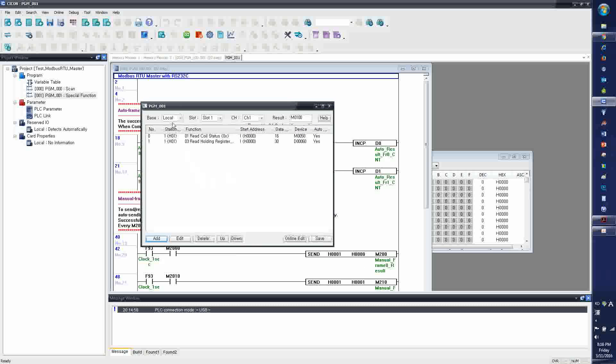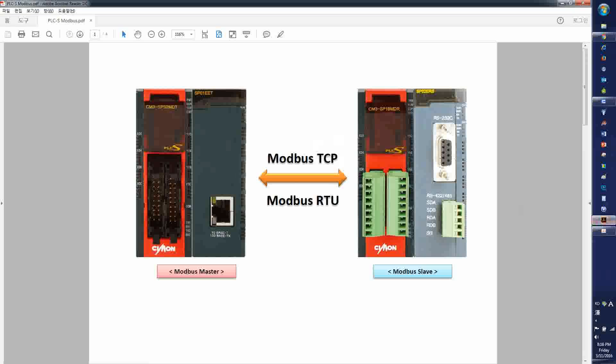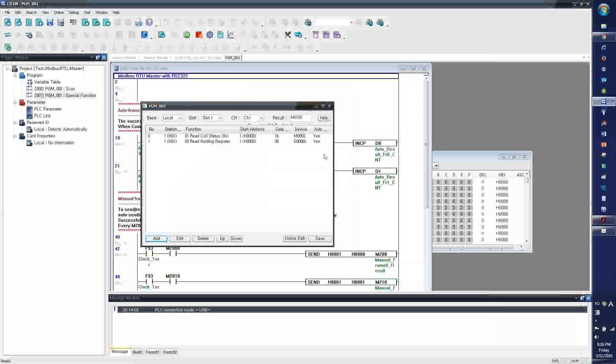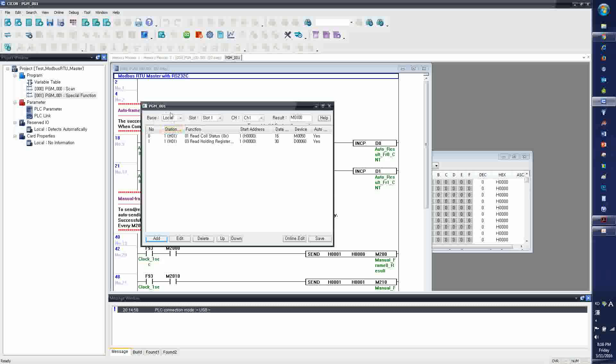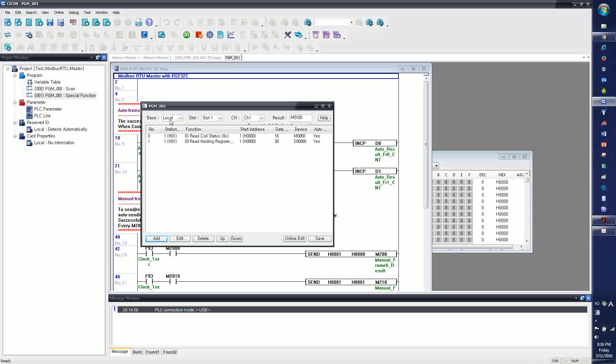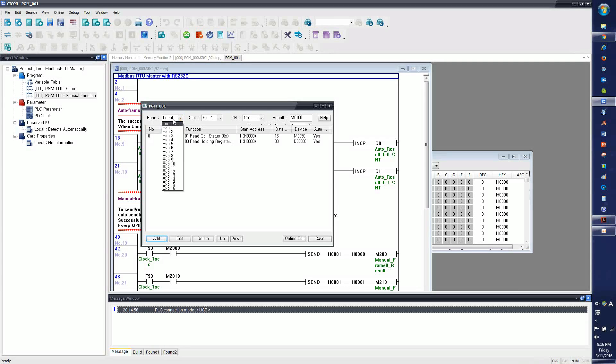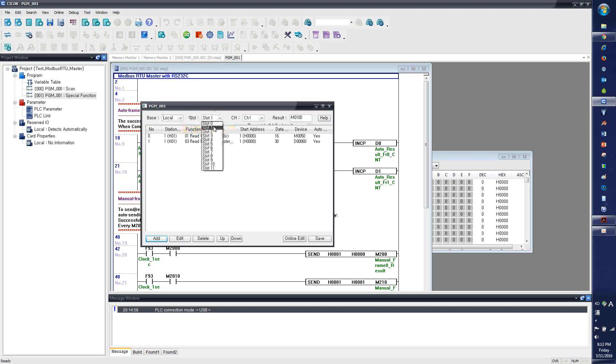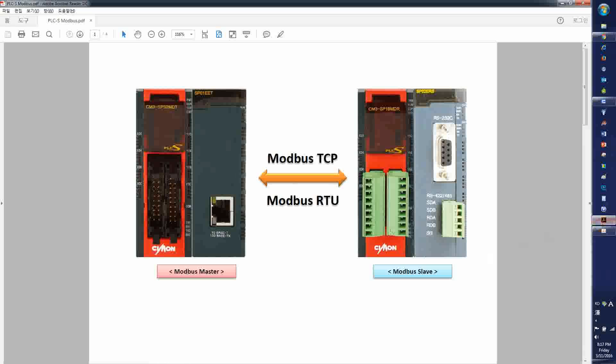Since my RTU Master is the serial module located right next to the CPU, it's going to be the local base, because CM3 PLC doesn't have any expansion, unlike the CM1 series. So it is local base, and slot number is 1, because it's next to slot number 0. The CPU is slot number 0.